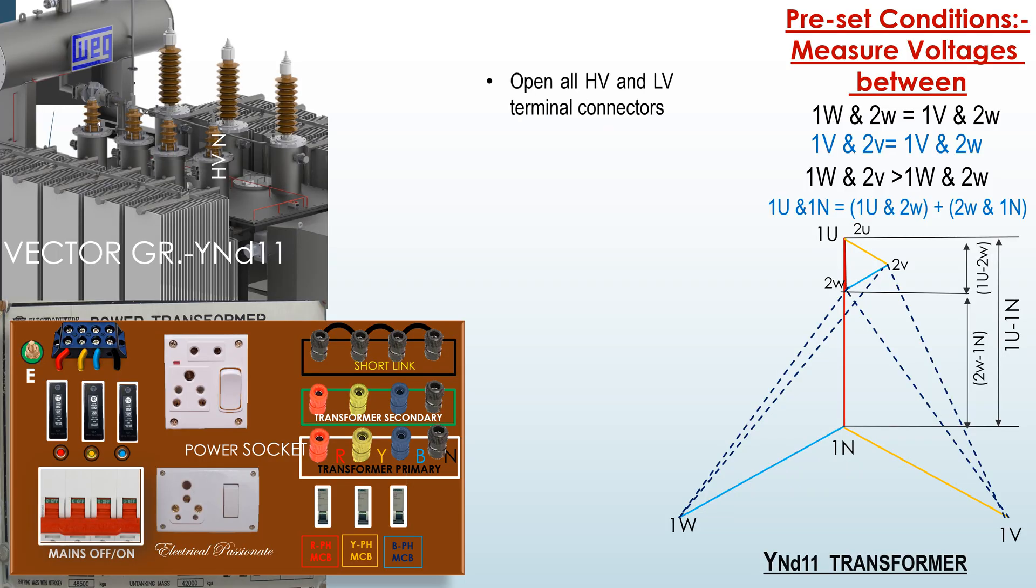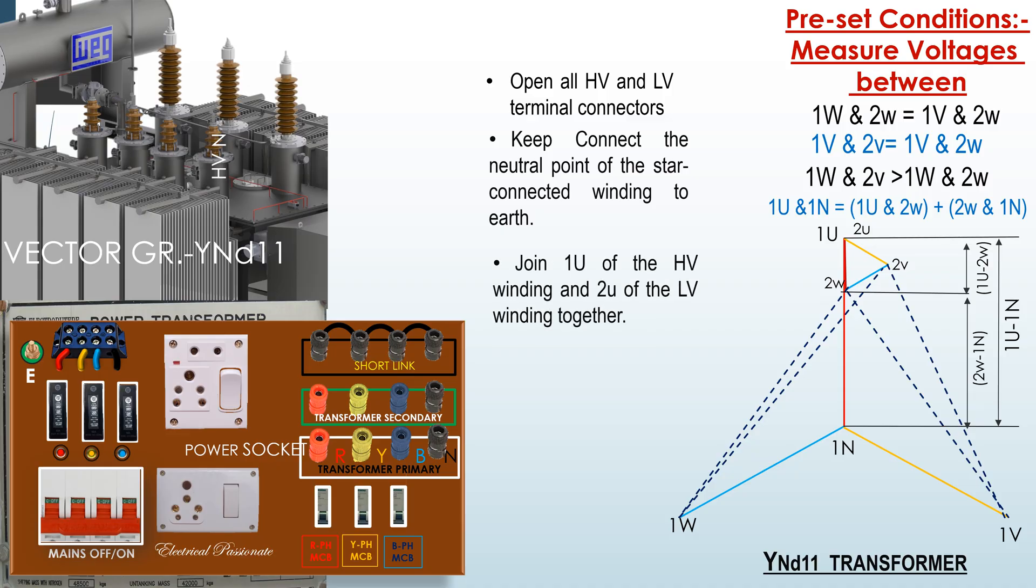Open all HV and LV terminals connectors. Keep connected the neutral point of the star connected winding to earth. Join 1U of the HV winding and 2U of the LV winding together at test board. Apply a 400 volt 3 phase supply to the HV terminals. Take care.